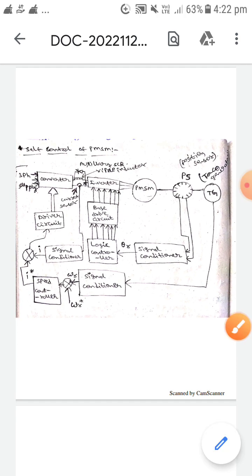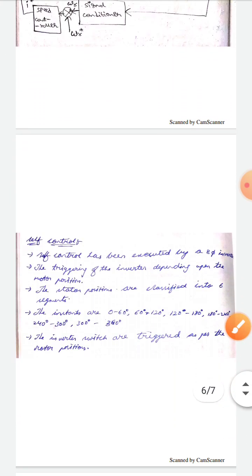Now let's discuss the self-control of permanent magnet synchronous motors. Here, self-control has been executed by a three-phase inverter. The triggering of the inverter depends upon the motor position. Also, the stator positions are classified into six segments: 0 to 60 degrees, 60 to 120 degrees, and so on, up to 300 to 360 degrees.